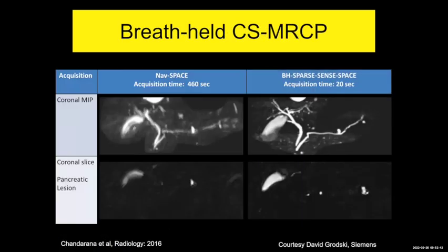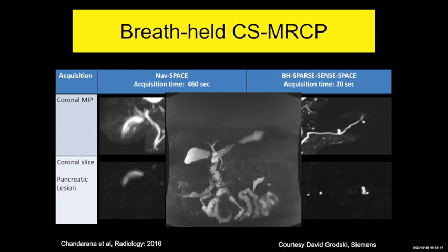And we've done this for a few different types of contrast. This is an MRCP acquisition. Again, MRCP is a heavily T2 weighted acquisition looking at pancreatic and biliary ducts, as well as pancreatic pathology. The information content is in a small number of voxels, and so we can really undersample our acquisition. We're only acquiring 5% of the k-space data and using compressed sensing methods for reconstructing that. These are the images that we've been doing at 1.5 and 3 Tesla, and we're starting to apply that on a lower field system, as we see here.